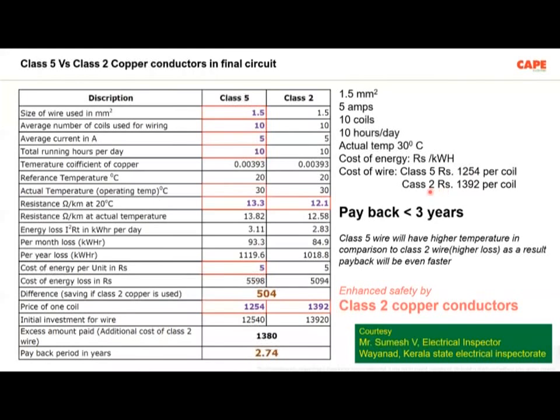Class 2 copper. The difference is the wires are thicker, the strands are thicker. As a result, probably maybe a little bit more copper has to be used. I'm not aware of such things. That is the job of the wire companies. Anyway, for a safety engineer, what is important is the offered resistance of that particular wire. Class 2 wire has a lesser resistance, higher cost.